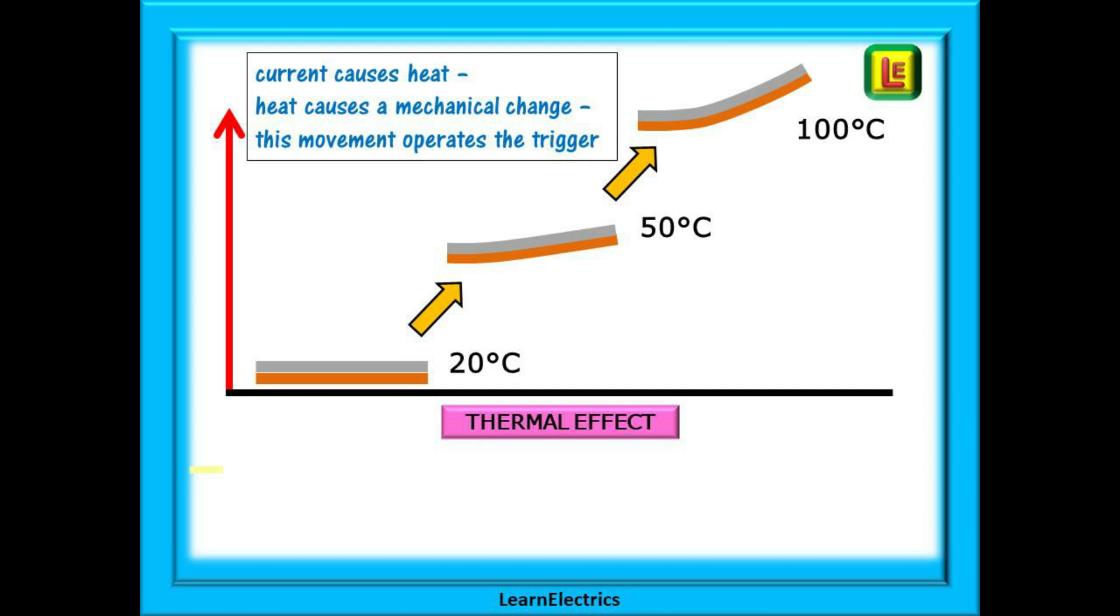The excess current causes heat to build up in the bimetallic strip and this heat causes a mechanical change, a movement in the strip. It is this mechanical movement that operates the trigger mechanism inside the MCB.